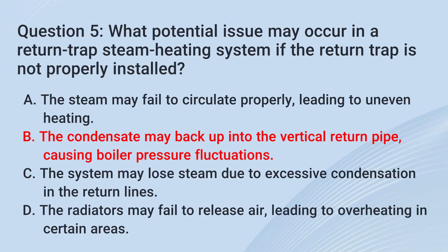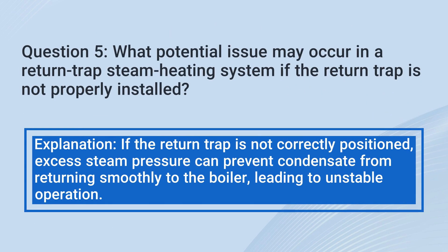The correct answer is B. The condensate may back up into the vertical return pipe, causing boiler pressure fluctuations. If the return trap is not correctly positioned, excess steam pressure can prevent condensate from returning smoothly to the boiler, leading to unstable operation.